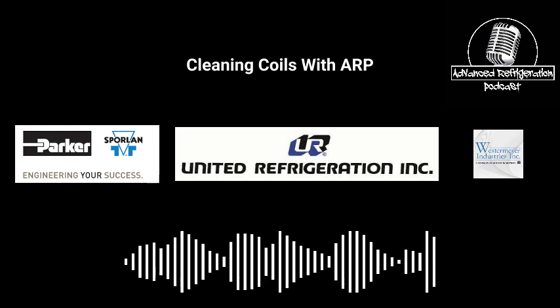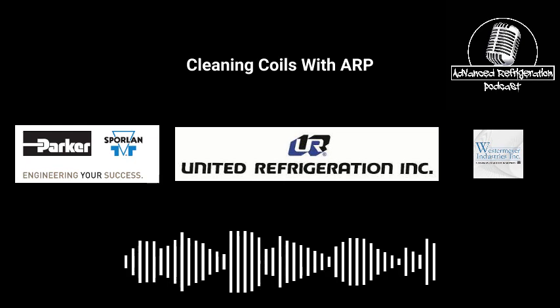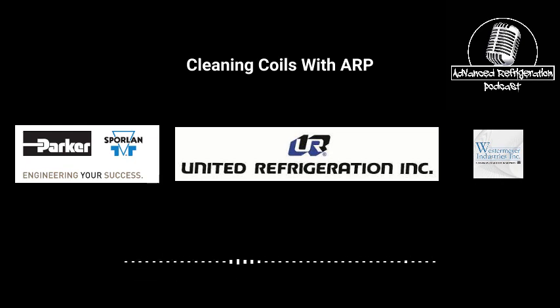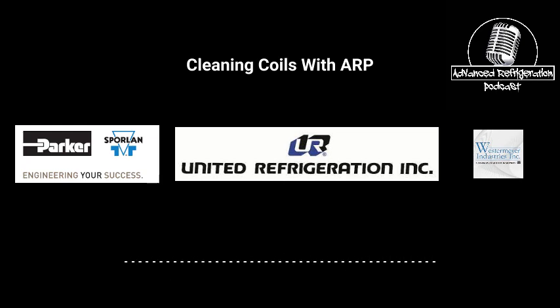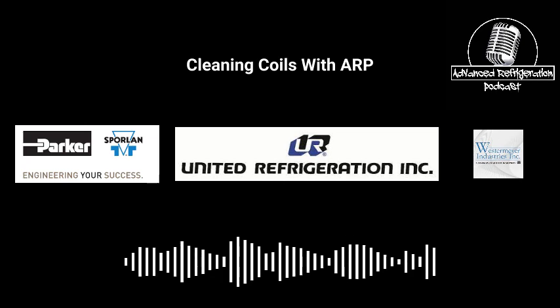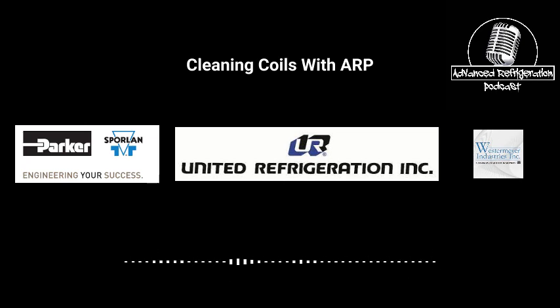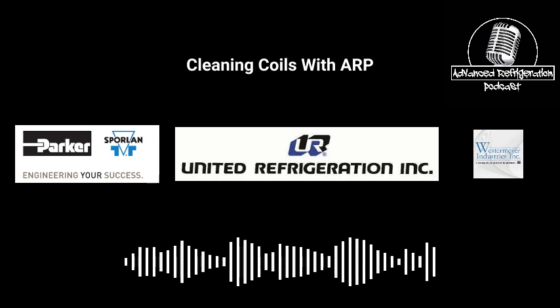Now, with that being said, I don't really think we should wait till the cottonwood flies. I think it should be done before that, and then service guys could brush coils off or hit them with water real quick and get the cottonwood off. Because in between that, then we're washing thick stuff off coils. The pressure washer guys haven't got there yet. So, me personally, I think we should be hitting these coils first thing and getting them all cleaned off before the cottonwood flies, because it's really easy to brush the cottonwood off a coil with a broom than it is to sit there and hit it with the power washer. And let's be honest, 90% of guys don't power wash a coil right.